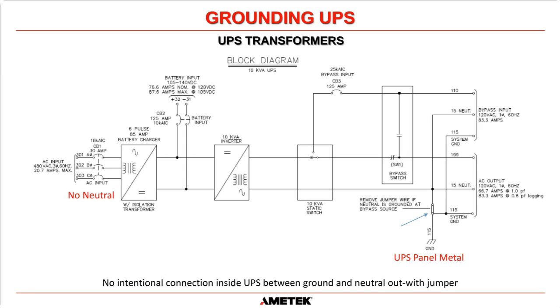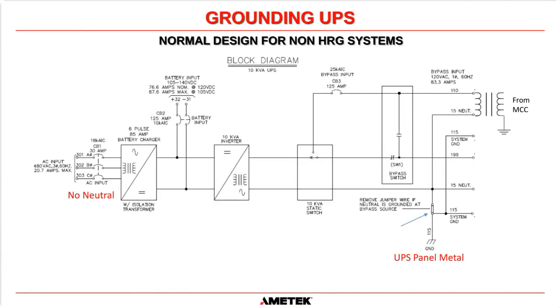And you can see that we have this jumper bar here that's in all of our UPSs, and it tells you what to do. It says remove jumper wire if neutral is grounded at the bypass source. Okay, and I'll explain that in a little more detail. Because what's going to happen is I've drawn this transformer here, but basically this is representing the feed from your MCC to the bypass of the UPS. Okay, now back at your MCC, this is the neutral, and this is the live or the hot. Okay, and back at your MCC, the neutral is going to be connected to ground. Okay, that's just a given.